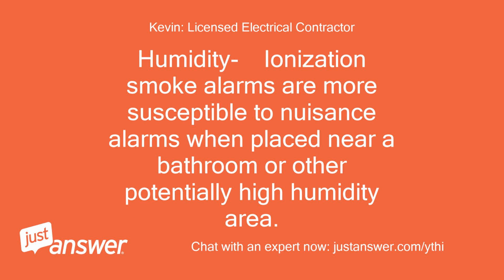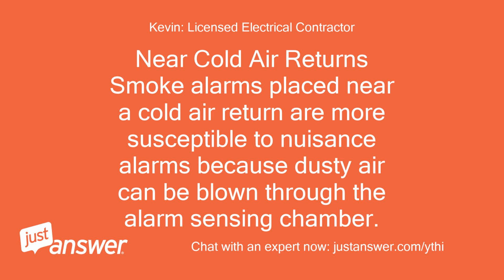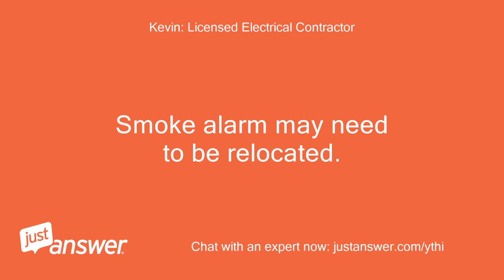Humidity: ionization smoke alarms are more susceptible to nuisance alarms when placed near a bathroom or other potentially high humidity area. Near cold air return: smoke alarms placed near a cold air return are more susceptible to nuisance alarms because dusty air can be blown through the alarm sensing chamber. Smoke alarm may need to be relocated.